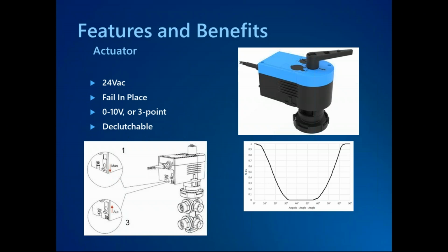And then controls, it's either 0 to 10 volts modulating or it's 3-point floating. And the 3-point floating is more or less what we consider on-off because you're going to run the cycle time for 30 seconds until it's fully closed and another 30 seconds to open up on the heating side. So it is floating in some sense because we have these 3 points that we need to hit: full heating, full cooling, and full isolation. But we're really just effectively doing on-off with all those points.